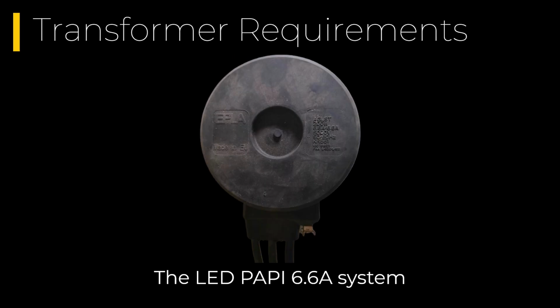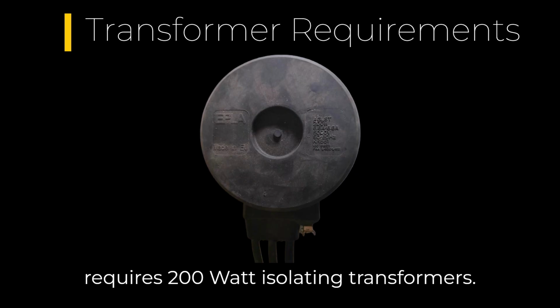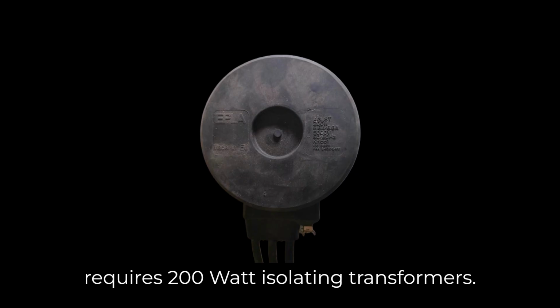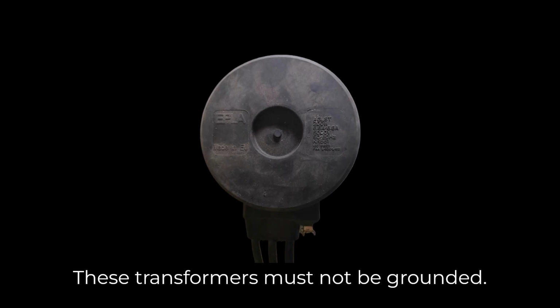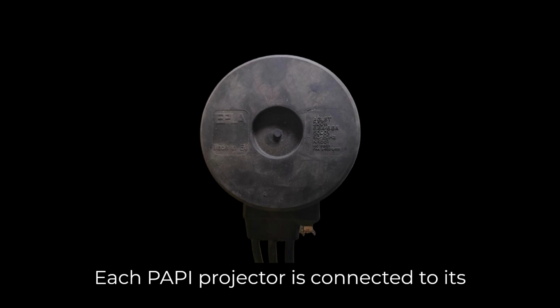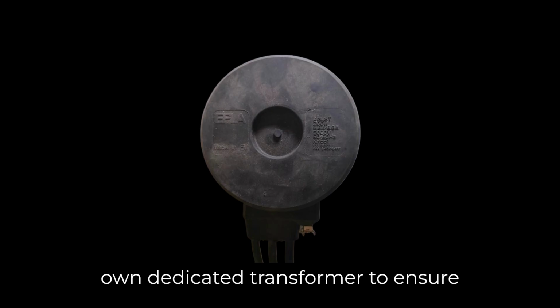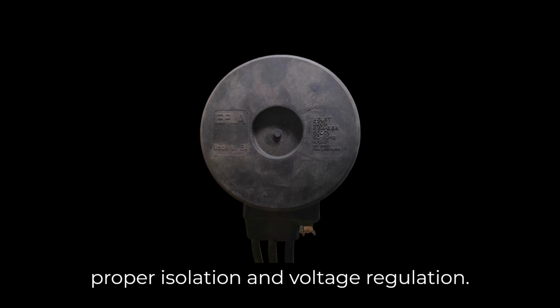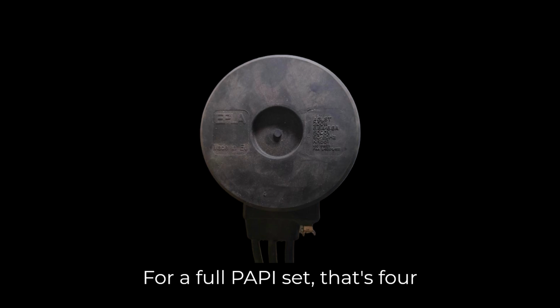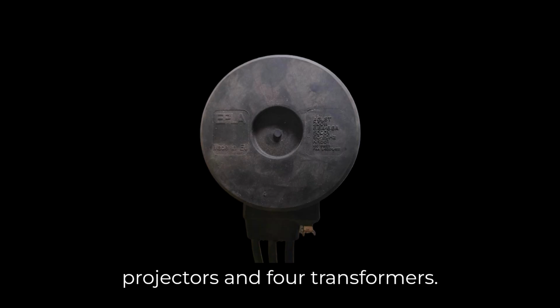The LED PAPI 6.6A system requires 200-watt isolating transformers. These transformers must not be grounded. Each PAPI projector is connected to its own dedicated transformer to ensure proper isolation and voltage regulation. For a full PAPI set, that's 4 projectors and 4 transformers.